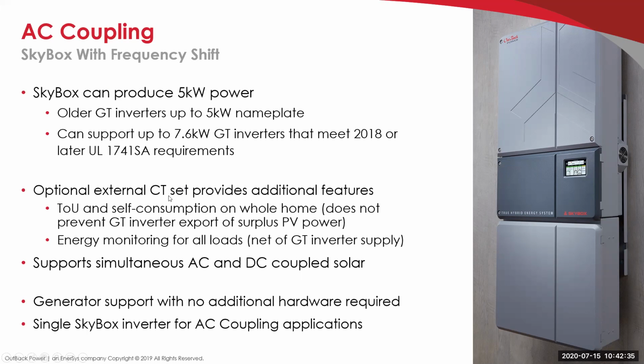And then there's the optional external CT. So when you are grid connected, when you're not in off-grid mode, you can still use some of the time of use and self-consumption functions of that. And one of the things that's unique also, I did some testing using an SMA inverter, the UL1741 SA compliant, and we've had both AC and DC coupled solar going to it. And it's kind of interesting when it's in the off-grid mode where we're acting like the grid source to the grid-dependent inverter. It takes that AC coupling power, and when we reduce the load down, it would start curtailing the DC coupled first, and before it would start curtailing the AC coupled portion of it. And it worked really slick.